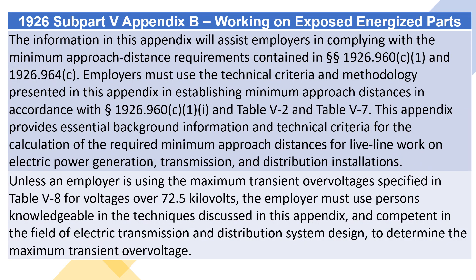The information in this appendix will assist employers in complying with the minimum approach distance requirements contained in Sections 1926.960(C)(1) and 1926.964(C). Employers must use the technical criteria and methodology presented in this appendix in establishing minimum approach distances in accordance with Section 1926.960(C)(1) and Table V-2 and Table V-7. This appendix provides essential background information and technical criteria for the calculation of required minimum approach distances for live-line work on electric power generation, transmission, and distribution installations.